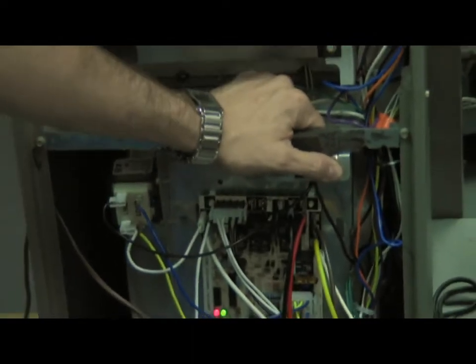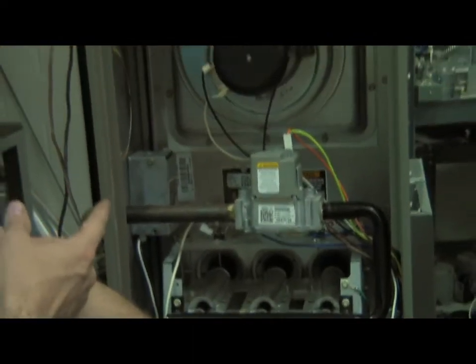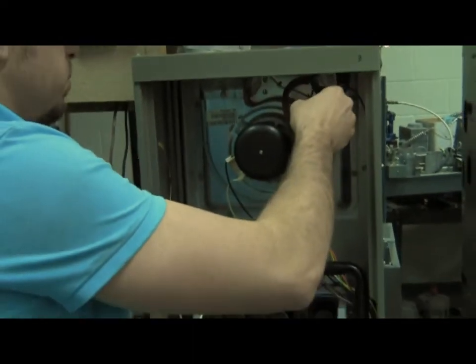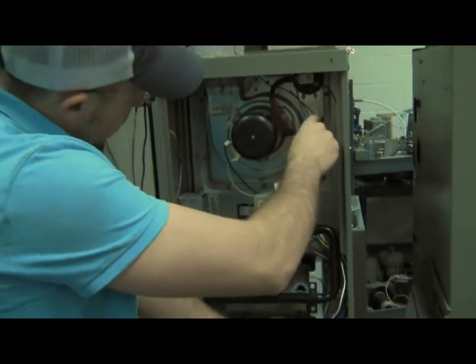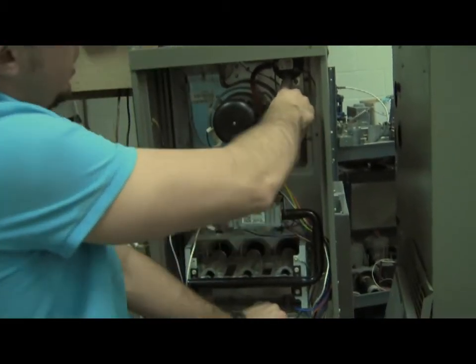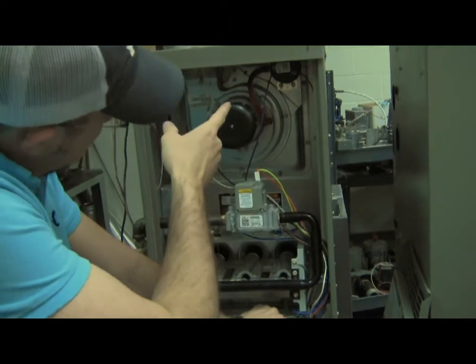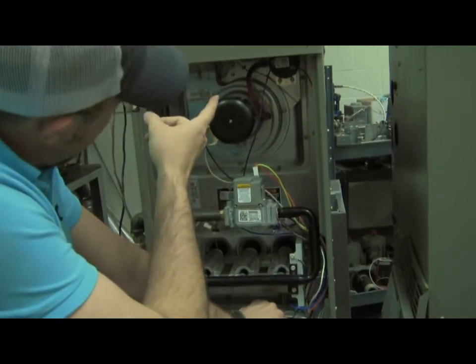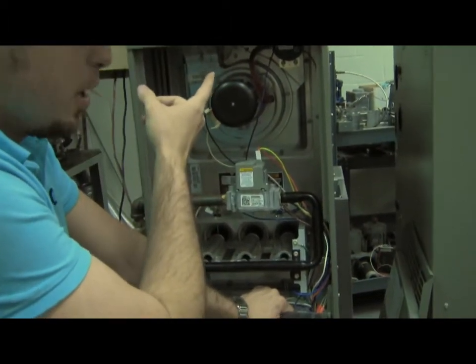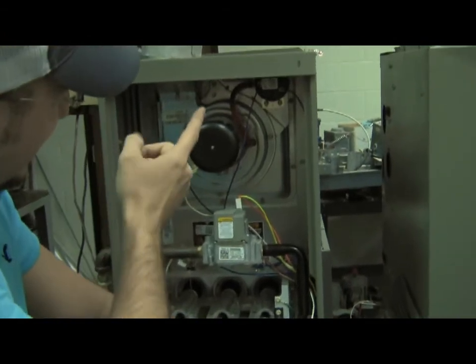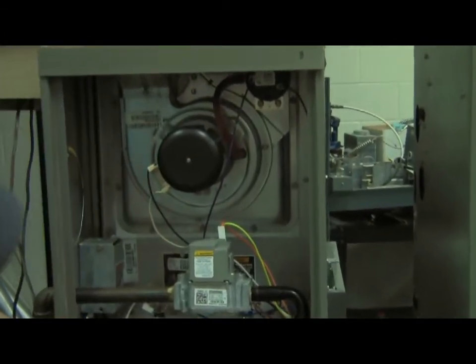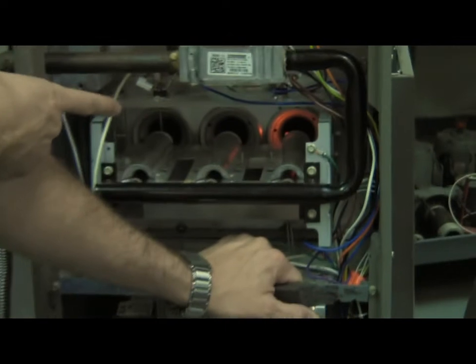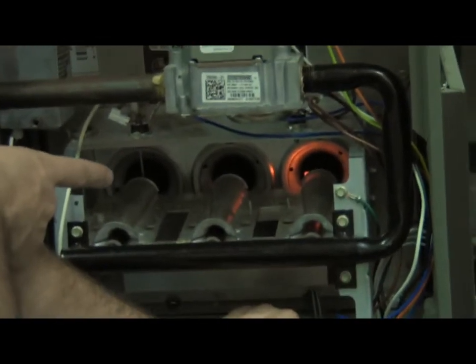First step is your induced draft motor comes on. The induced draft motor creates a negative pressure on the, what the hell's the name of that thing? Pressure switch. Pressure switch. The pressure switch closes. Once the pressure switch closes, it turns on your igniter.